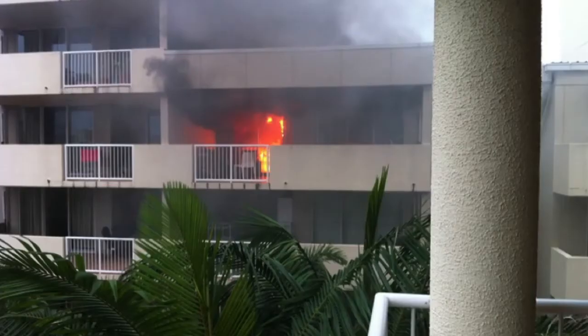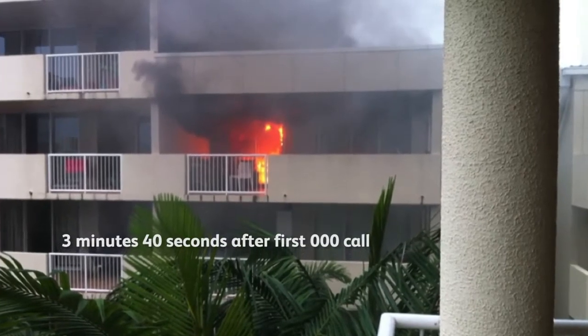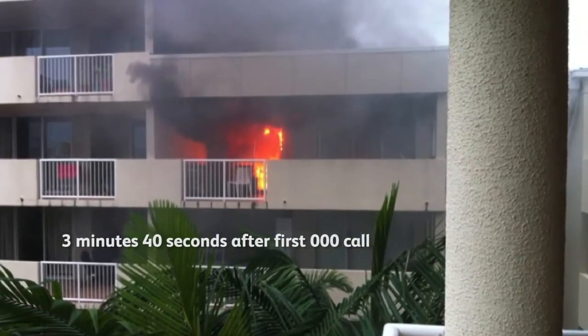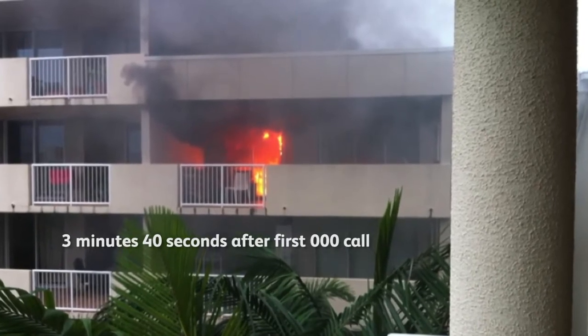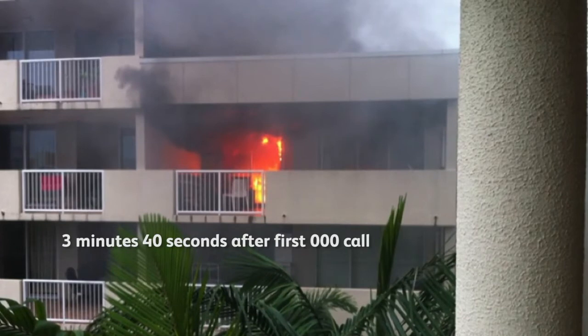for that smoke to start spreading, and obviously the heat and fire spread very quickly. Two minutes later, the next photograph now shows that it's pretty much flashed over in that room. It looks like it's penetrating out through the glass onto the balcony. But at that stage now, there's a large amount of smoke coming out through the roof space. And initially we were looking for the possibility that it may have spread out through the balcony and up through the non-fire rated ceiling on the balcony. But from those photographs, I think it's quite clear that it has already actually breached that fire rated ceiling.